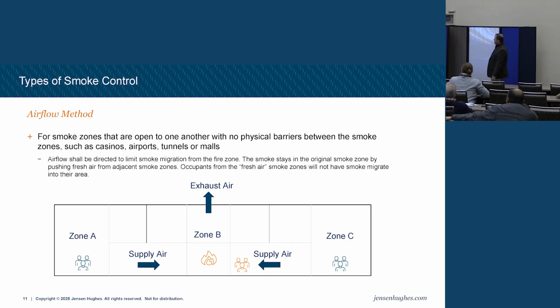All right, so airflow method. So these are an example of this, and really similar to an atrium, right? But the airflow method would be, an example would be BWI Airport. Did anybody fly in by chance? Or I assume you've all been through BWI too, right? So you have different spaces, concourse A, B, C, the terminal building, all that stuff, right? There's no physical barriers to a lot of those spaces, but I have to keep the smoke out of one from getting into the other. The way we do that is force mechanical airflow and force the air to where the fire is, and then it pulls it out over the top of it, so the smoke doesn't spread throughout the building. That's the airflow method in a nutshell.